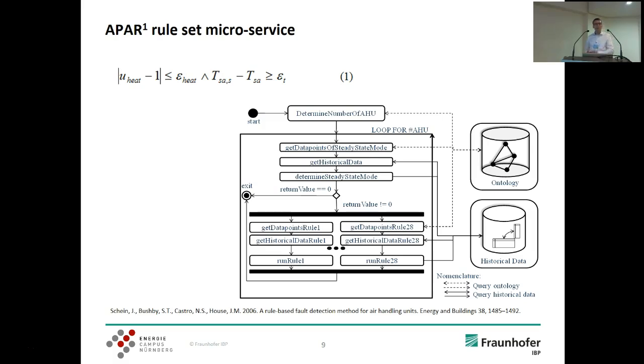...from the APAR rule set. This is one fault detection method where you use rule-based fault detection, evaluating a rule to determine if some technical equipment is in a fault state. So what this actually tells you is that this is a normalized heating control signal of the heating valve in the heating coil of an air handling unit.